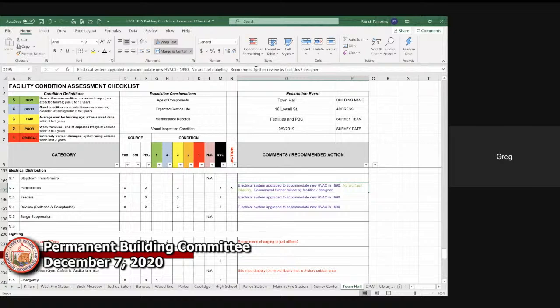The most prudent thing, though, would be to have a general label on all the panels that says danger, live voltage or high voltage, and then the electrical arc hazard. There's a generic arc flash sticker that could go on most of the panel boards, but that's about all you could do without a significant amount of cost and effort.